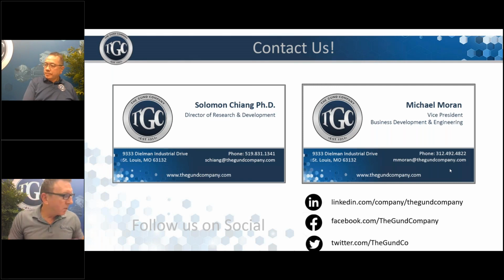Okay, maybe one more from our list of questions from previous. Let's see. How about this one? I think you also covered this a little bit, Solomon, from Chris. How do I know when the RTI test was done when I compare a UL yellow card? You don't, because that's proprietary information. And as I said before, you know when the yellow card was originally issued, for example 1985, and then it will show you the last revision date, but it doesn't tell you what was revised. And usually, if you have RTI and you like what you see, you don't test it again and again and again, and it's not part of the UL follow-up service.